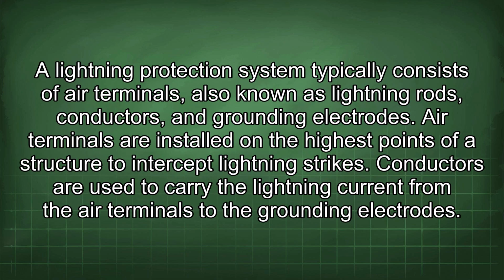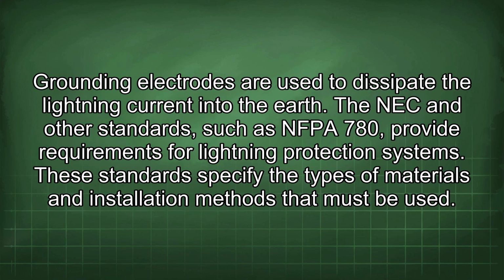A lightning protection system typically consists of air terminals, also known as lightning rods, conductors, and grounding electrodes. Air terminals are installed on the highest points of a structure to intercept lightning strikes. Conductors are used to carry the lightning current from the air terminals to the grounding electrodes. Grounding electrodes are used to dissipate the lightning current into the earth. The NEC and other standards, such as NFPA 780, provide requirements for lightning protection systems. These standards specify the types of materials and installation methods that must be used.